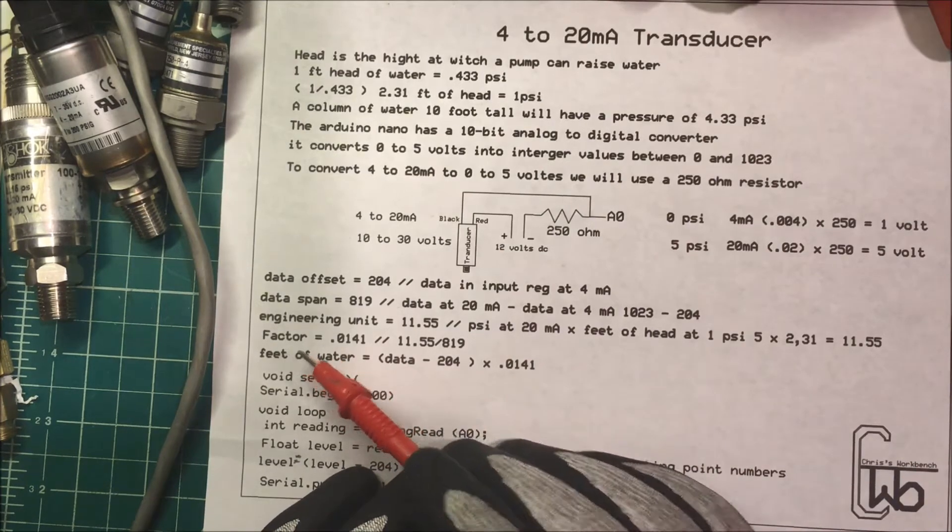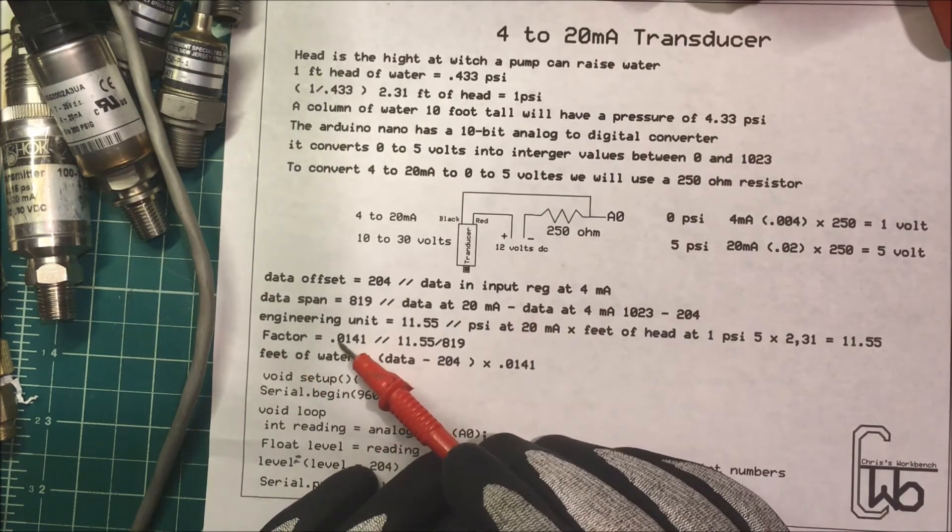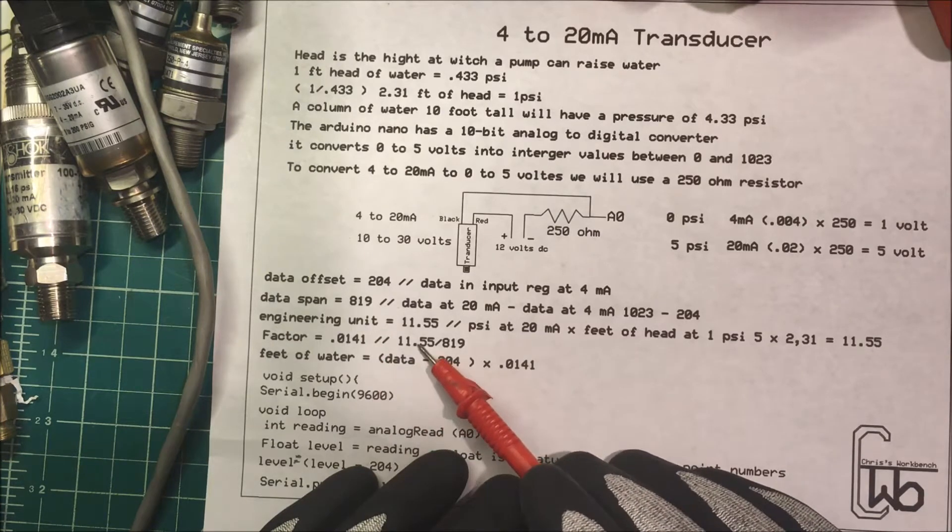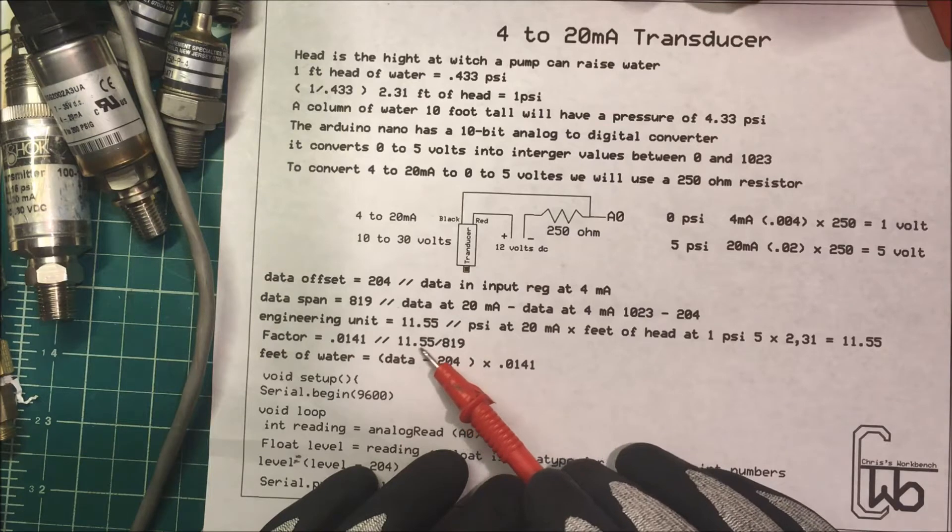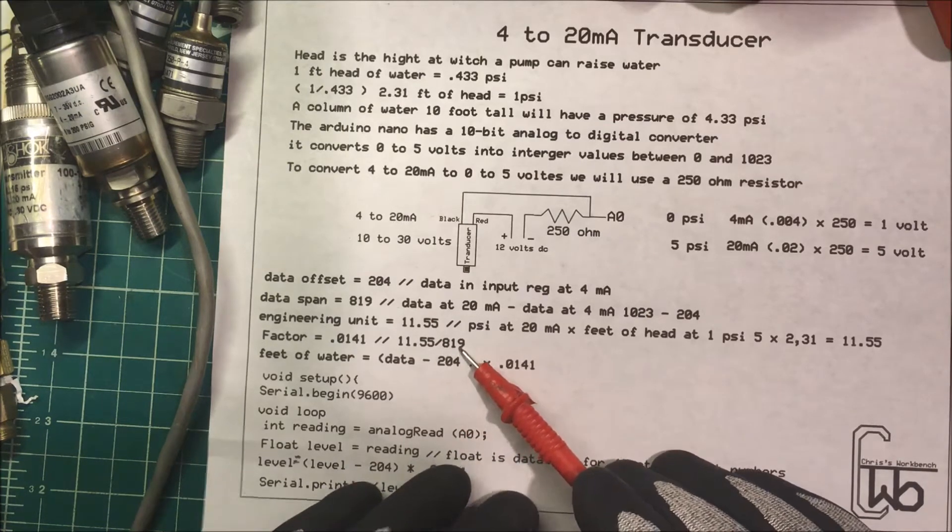Now we have a factor here and that's 0.0141, and we get that by dividing this engineering unit by our data span. 11.55 divided by 819.